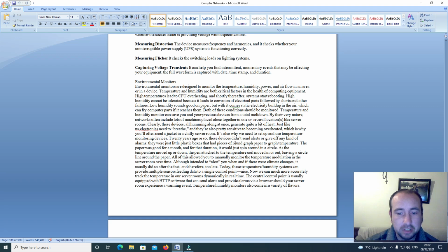20 years ago or so, these devices didn't send alerts or give off any kind of alarms. They were just little plastic boxes with pieces of round graph paper to graph temperature. The paper was good for a month, and for that duration it would spin around in a circle. As the temperature moved up and down, the pen attached to the temperature coil moved in or out, leaving a circle line around the paper. This allowed you to manually monitor the temperature modulation in the server room over time, though it was intended to alert you when there were climate changes. It usually did so after the fact, and therefore too late.